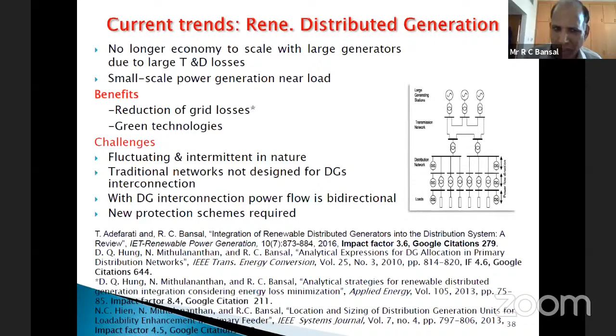So what is the issue with bidirectional power flow? Protection is one of the biggest issues, because in the past we had a simple protection system. Single directional relays were used for protection. But when the power flow becomes bidirectional, the existing protection scheme may not work well. So we may need significant modification in the existing protection schemes, or the protection system may require complete replacement. So protection is one of the major challenges. Then the traditional network has not been designed for these intricacies, and these sources are fluctuating and intermittent in nature.